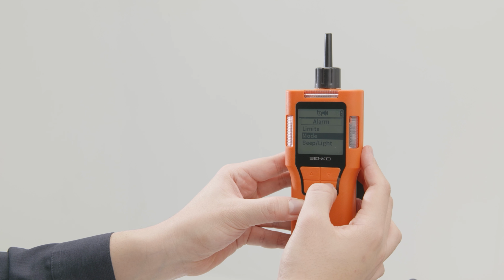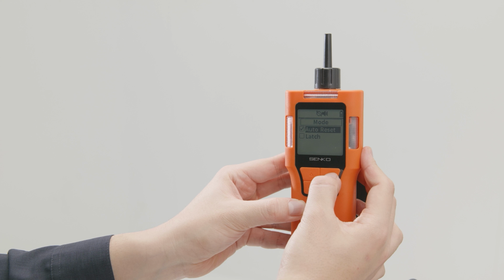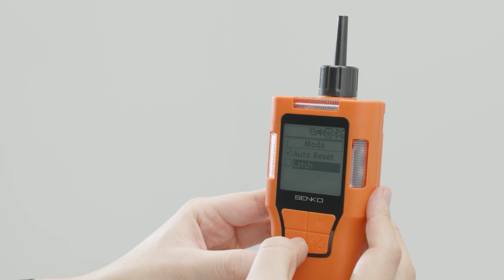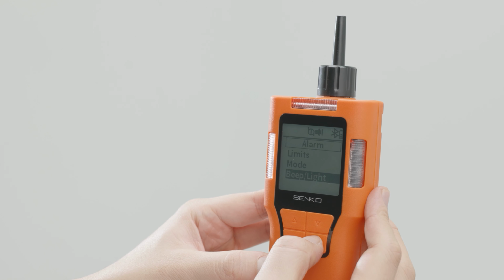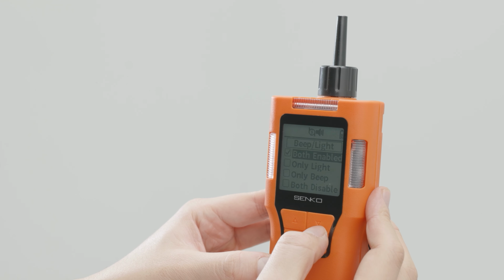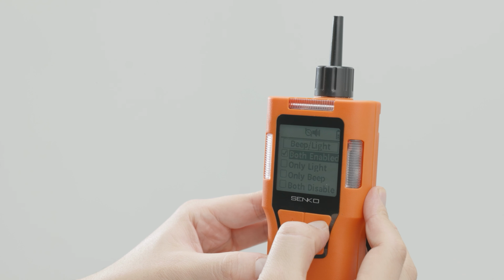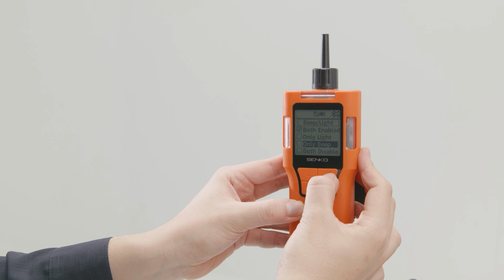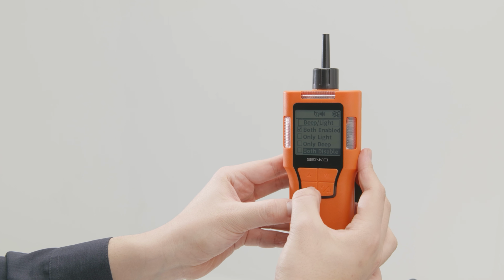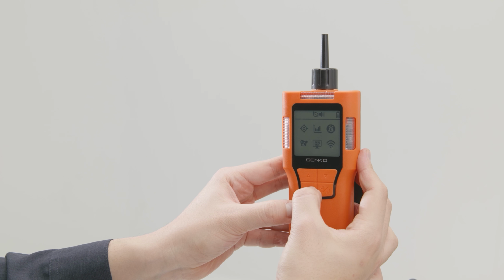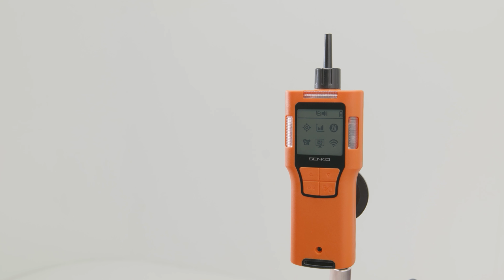vPro supports 2 alarm modes: Auto Reset and Latch. In Auto Reset mode, when gas concentration returns to the normal range, the alarm is automatically released. And in Latch mode, it must be released manually by pressing the ESC button. Also, depending on the working environment, the alarm sound, LED display, and vibration alarm can be set individually. So the warning method can be optimized according to the noise or visibility conditions of the working environment.